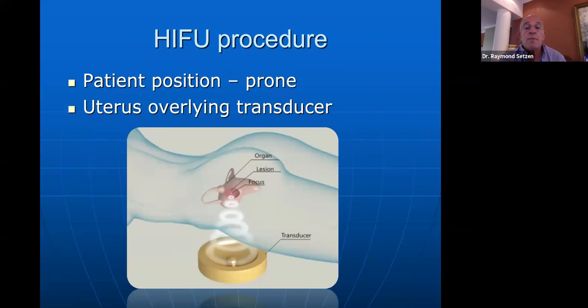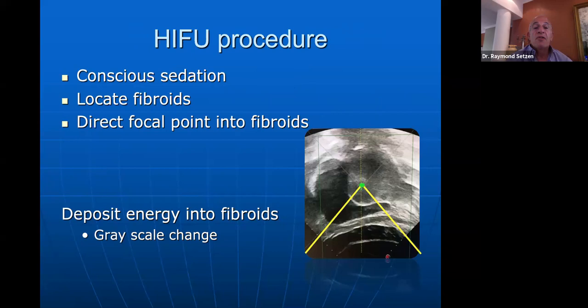The patient is then administered conscious sedation. The fibroids are located using the B-mode probe situated inside the concave transducer. Once we find the fibroids, we direct the focal point into them and start depositing energy into the fibroids, monitoring the treatment by using grayscale change.